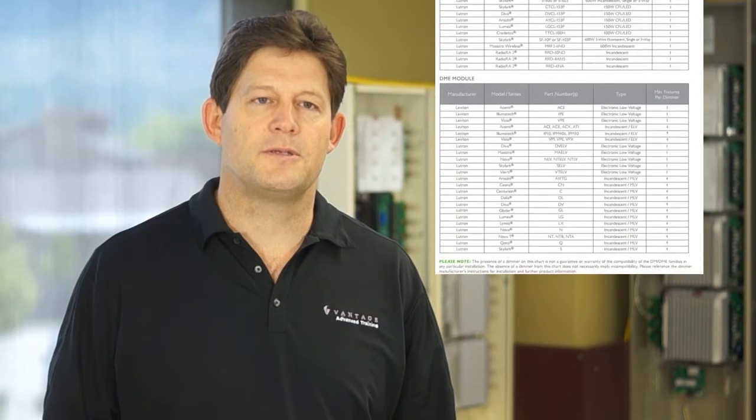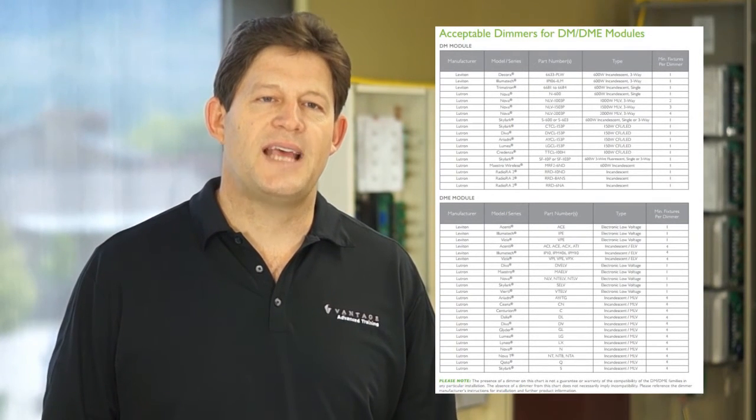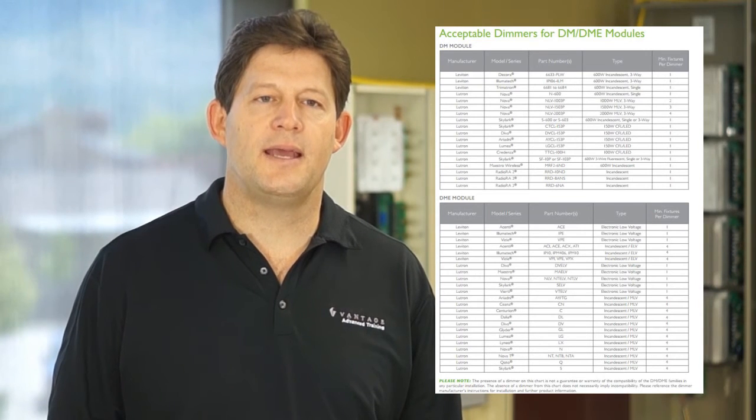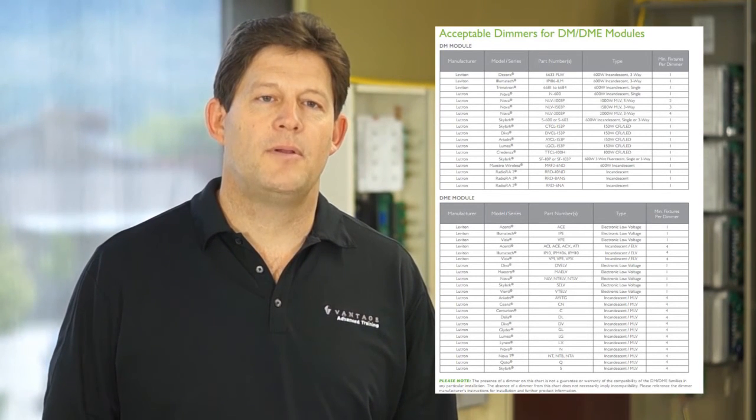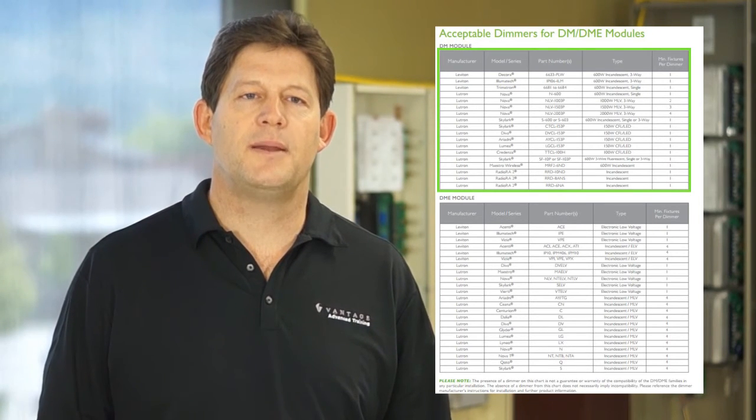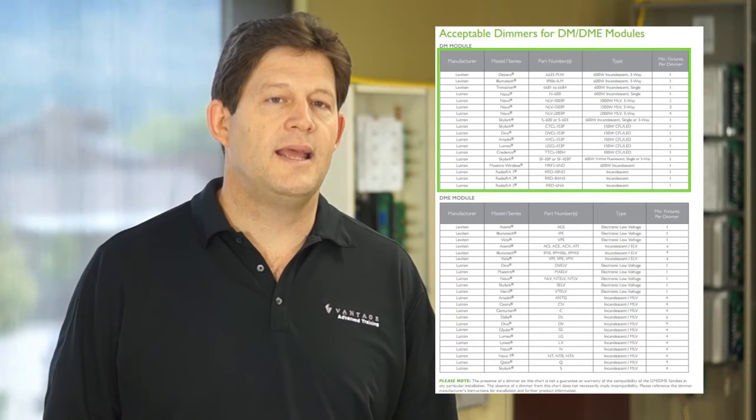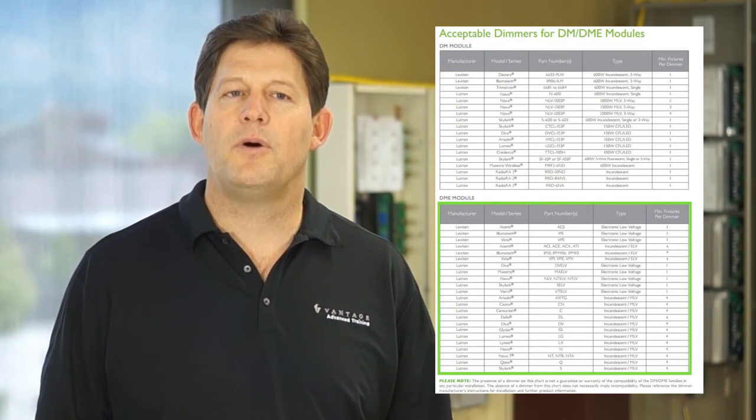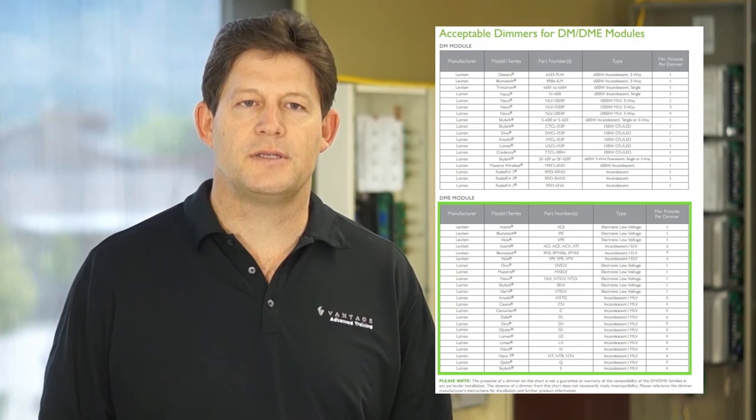Sometimes a manufacturer doesn't state the dimming technology, but instead gives a list of acceptable dimmers. We may need to examine the acceptable dimmers to determine what dimming technology they use. In this example, by examining the dimming technology used by the listed acceptable dimmers, we determined that the DM module is forward-phase compatible, and the DME module is compatible with both forward-phase and reverse-phase dimmers.